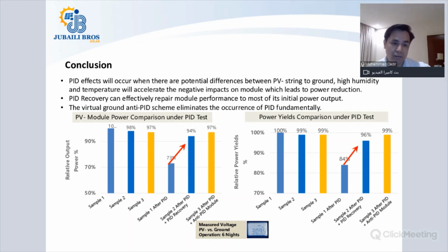After the PID issue has occurred, you can see that the three samples shown here were giving a high generation of power, and after that, when there was no PID solution used in the PV plant, it had degraded to 73% of its power output after 6 nights of operation, by the way. And after the PID recovery module was applied, the power output of the inverter increased to 94% now.